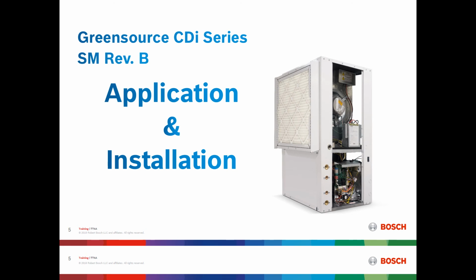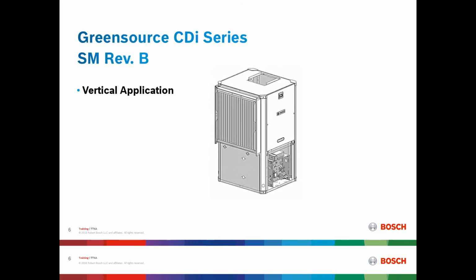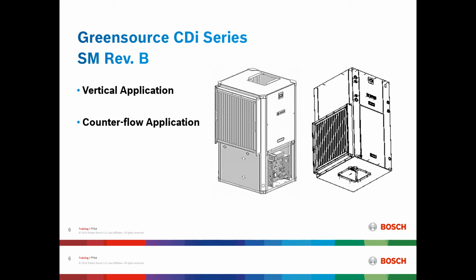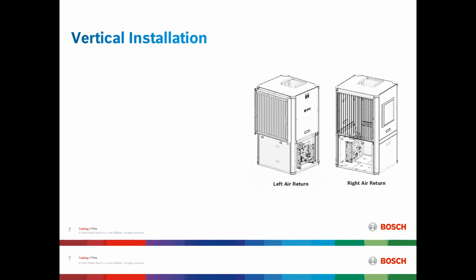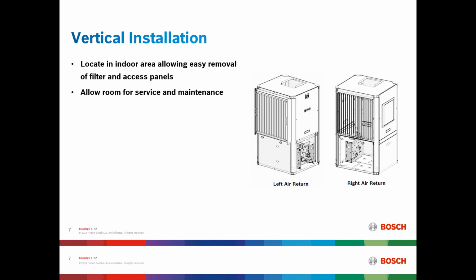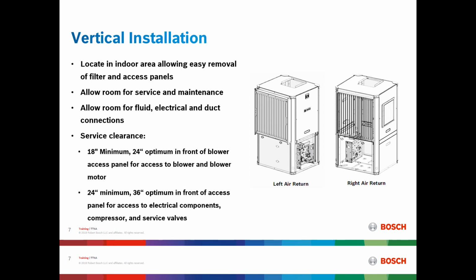Now let's focus on application and installation of the SM Rev B unit. This particular model can be configured in a vertical application or in a counterflow application if ductwork is below the unit. In the vertical situation, the installation will require that the machine be located in an area allowing easy removal of filters and access panels, allowing room for service and maintenance, allowing room for fluid, electrical, and duct connections. All machines have service clearance criteria, which is commonly dictated by local codes and ordinances. However, Bosch will provide recommendations for service clearance in all of the available installation, operation, and maintenance manuals provided with the unit. For the vertical unit, it is available in left-hand and right-hand return air configurations.